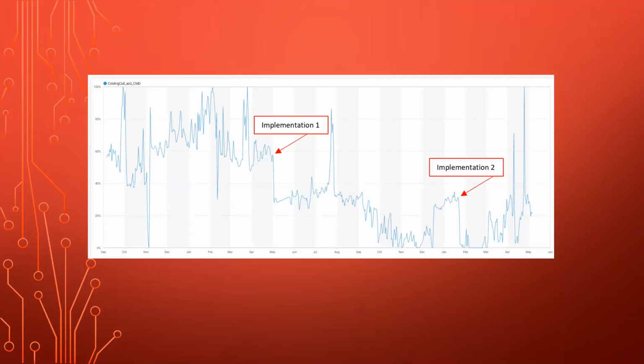This slide really illustrates how we used the software in the retro commissioning process. We were heavily focused on the Historian app. So for me as an energy manager, instead of coming in and looking at a list of faults every day, I actually come in and look at air handler by air handler, the consumption pattern and historical trends. This graphic illustrates the chilled water valve command, and we can see in various phases of the retro commissioning that we were really able to move the needle on reducing our chilled water consumption.